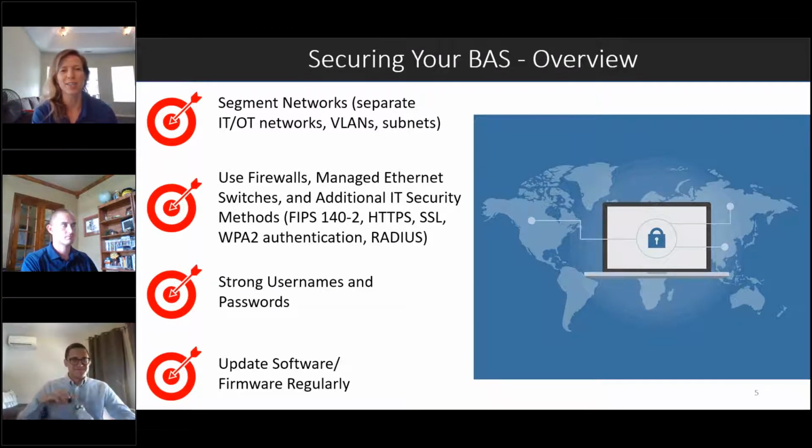Definitely, as Grant said, change the default username and password. You can't believe how many customers have the same username and password as that default manufacturer uses. So step one, change that. And then each user should have a distinct username and password. You can also assign different access levels for different users within your system. So maybe some only get view-only privileges, where some are able to make different adjustments and overrides.